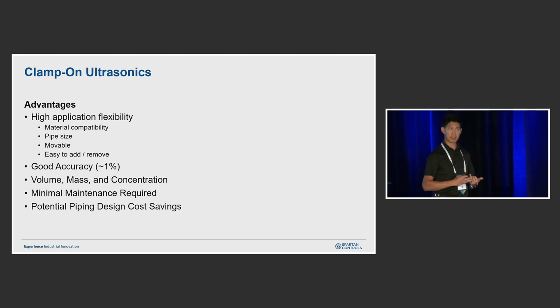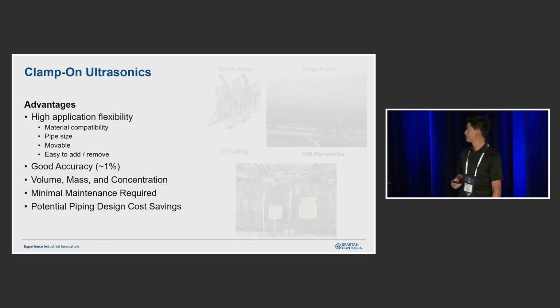Accuracy's decent, I would say. So we're typically sitting about 1%. We can do volume, mass, and concentration if we need those things. The maintenance is quite minimal. We don't have to worry about erosion or corrosion unless your pipe is literally bursting. Then we got probably other issues. And then, of course, we have, like I said, a lot of flexibility around piping. So you don't really have to make a bunch of changes. We can just use what we have.